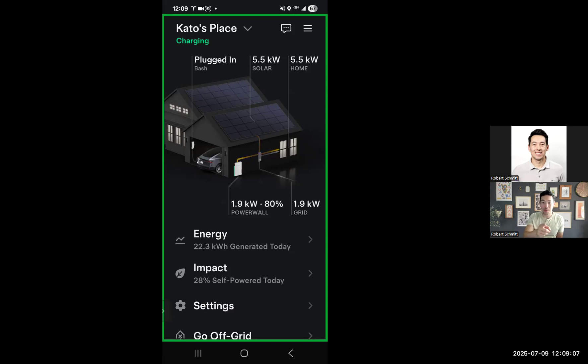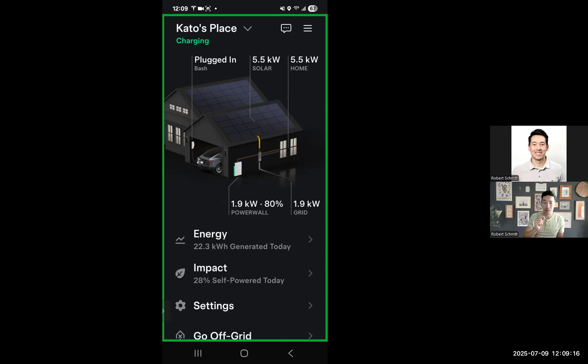So as you can see, my Powerwall is not fully charged. It is midday, 12 p.m. I have really good production from my 8 kilowatt system, and only 1.9 kilowatts is being pushed to this Powerwall, even though it supports almost 6 kilowatts being pushed into the Powerwall. And this should have been charged last night.